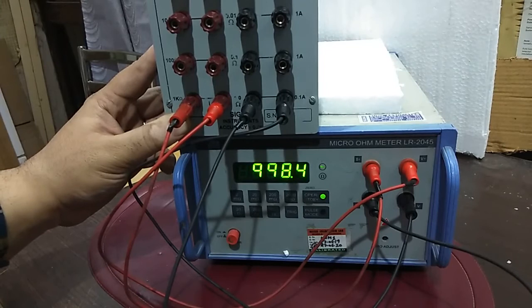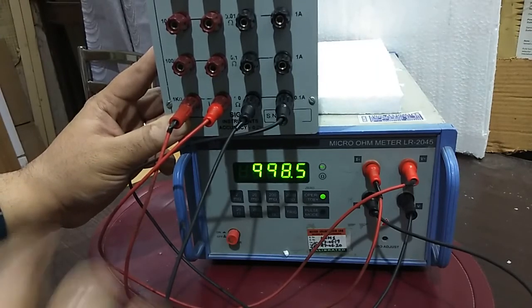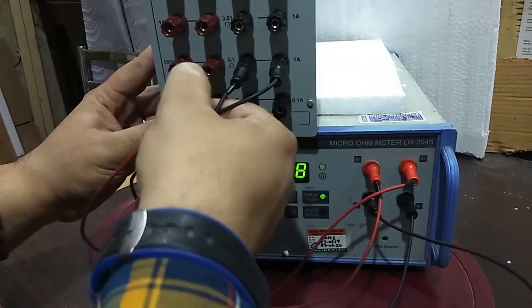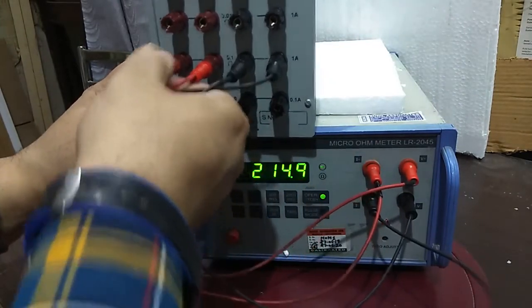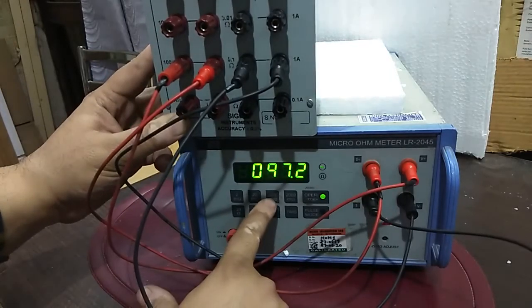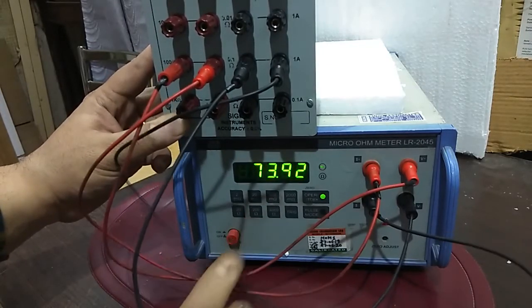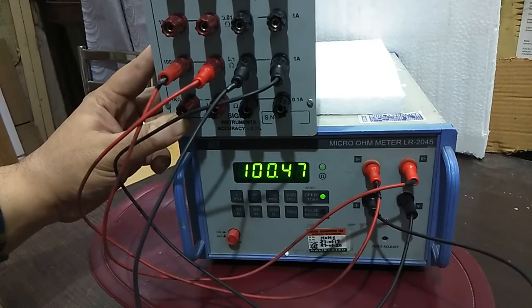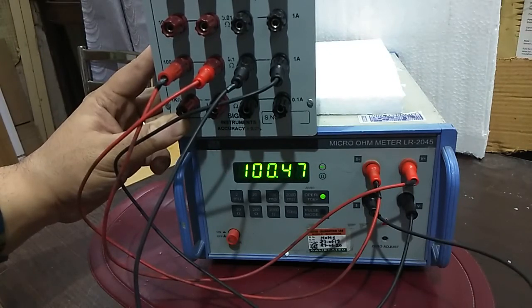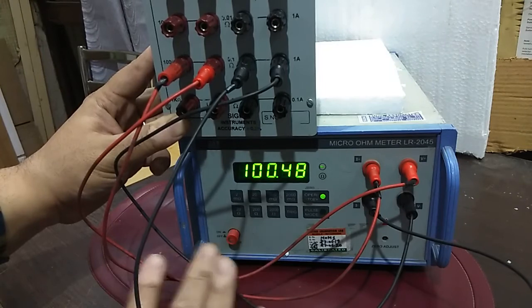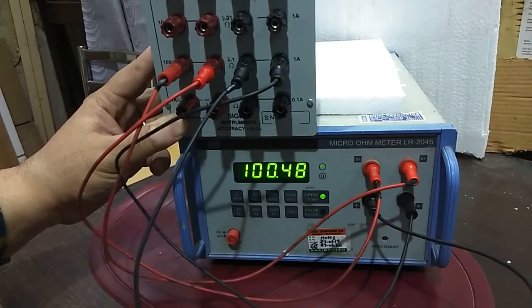This is thousand milliohm, the results are fine. Now it's hundred milliohm. Let's see the results. Results are going good. Yes, it is showing hundred point four eight. The four and a half digit results are okay and doing good.